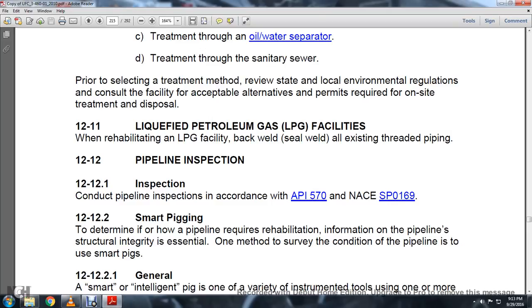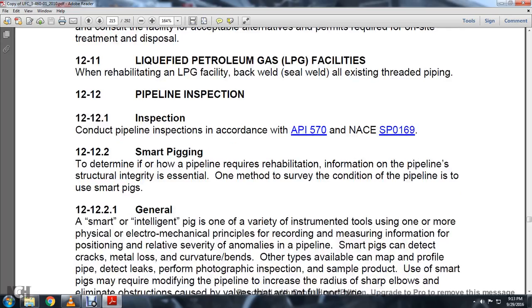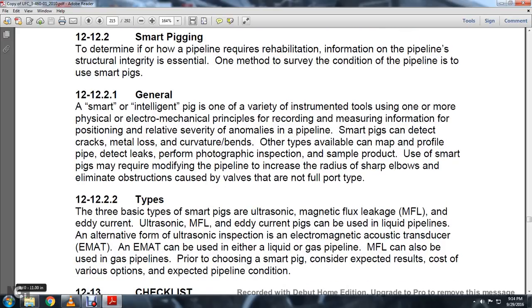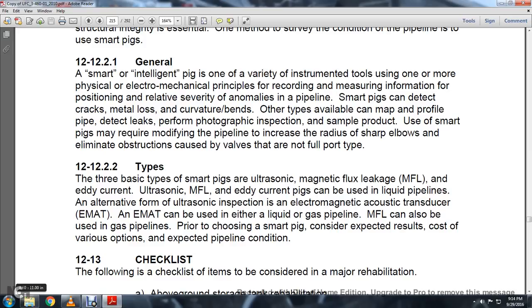Section 12-12-2: Smart pigging. To determine whether a pipeline requires rehabilitation and to assess structural integrity, use smart pigs. A smart or intelligent pig is an instrumented tool using physical, electrical, or mechanical principles to record and measure information along the pipeline. Smart pigs can detect cracks, metal loss, curvature, bends, and other anomalies, and can map profiles, detect leaks, perform photographic inspection, and sample product. Using smart pigs may require modifying pipes by increasing the radius of sharp elbows and limiting obstructions caused by valves that are not full-port. Section 12-12-2-1: Types. The three basic types of smart pigs are ultrasonic, magnetic flux leakage, and eddy current. An alternative form of ultrasonic inspection is the electromagnetic acoustic transducer (EMAT), which can be used in either liquid or gas pipelines. Prior to choosing a smart pig type, consider expected results, cost, and various options.